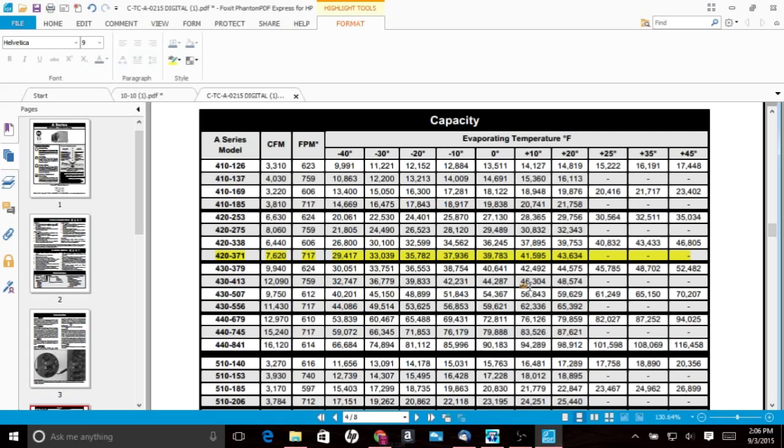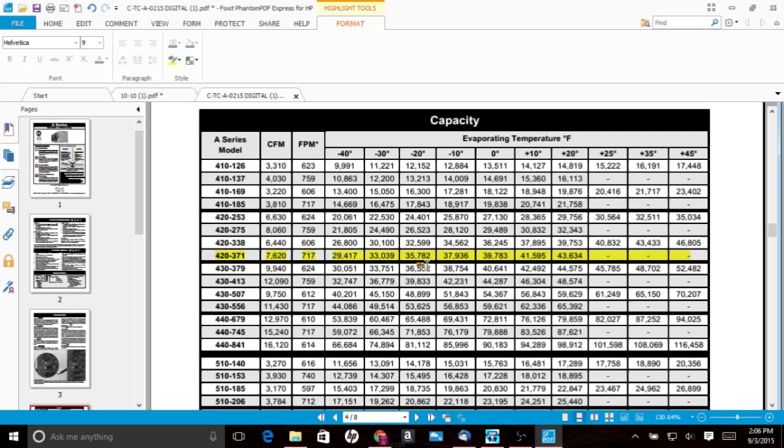So we see right here that we have minus 20 evap temp would put us at right at 35,782 BTUs. Minus 10 evap, 37,936 BTUs. So dividing that by 12,000, we get just at 3 tons of refrigeration, you know, anywhere in that area, zero to 10 degree box temp.